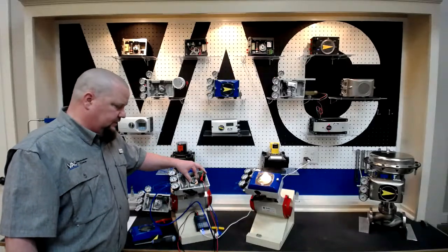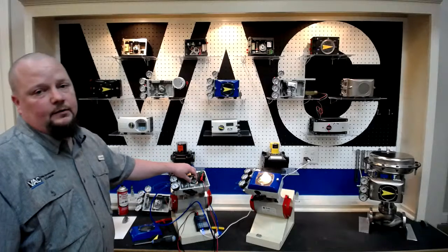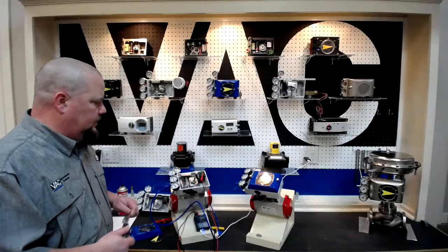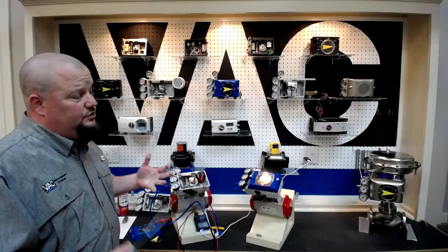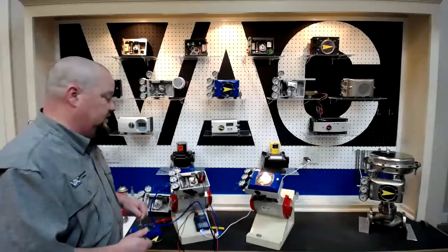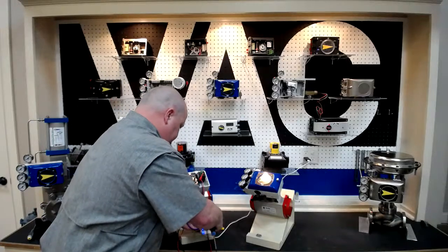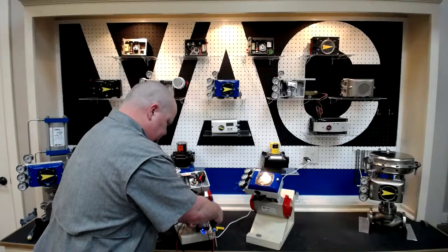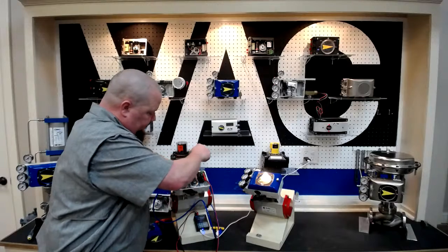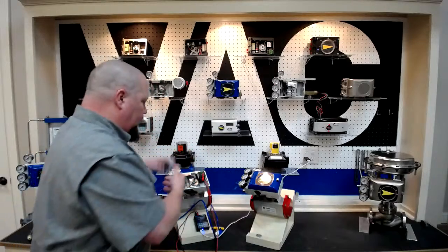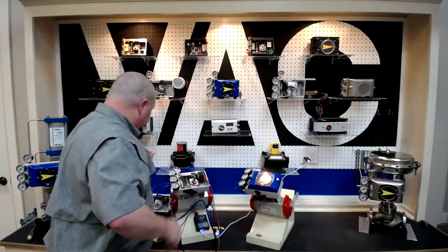But back to, like we said, by far and away the biggest issue we have on these is initial setup of the cam. Very seldom, occasionally, we might see one come loose after it's been in service for a while, but that's generally because it wasn't installed properly initially. Again, the things we're speaking to now are really mainly all setup issues.